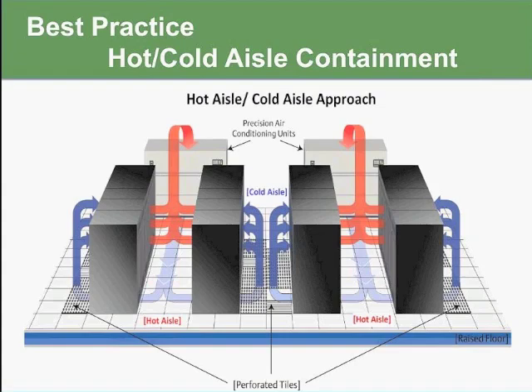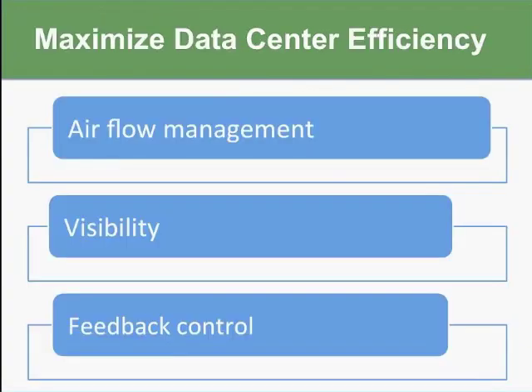And furthermore, you're generally able to raise the supply temperature of your CRAC unit and still have the exact same cooling efficiency that you have at a lower temperature where you don't have good airflow management. It's counterintuitive, but what's nice about that is you're achieving the same ends with much, much less energy. And in addition, if you want to play with higher set point temperatures, you can do that as well. So that's kind of a segue into an aside here, which is that best practices in airflow management from an operational perspective will also get you significant data center energy efficiency gains. You might be able to see your PUE, your data center efficiency, drop from a 2 down to, say, a 1.4, so that you can get a 30 to 60% reduction or improvement in your energy efficiency.